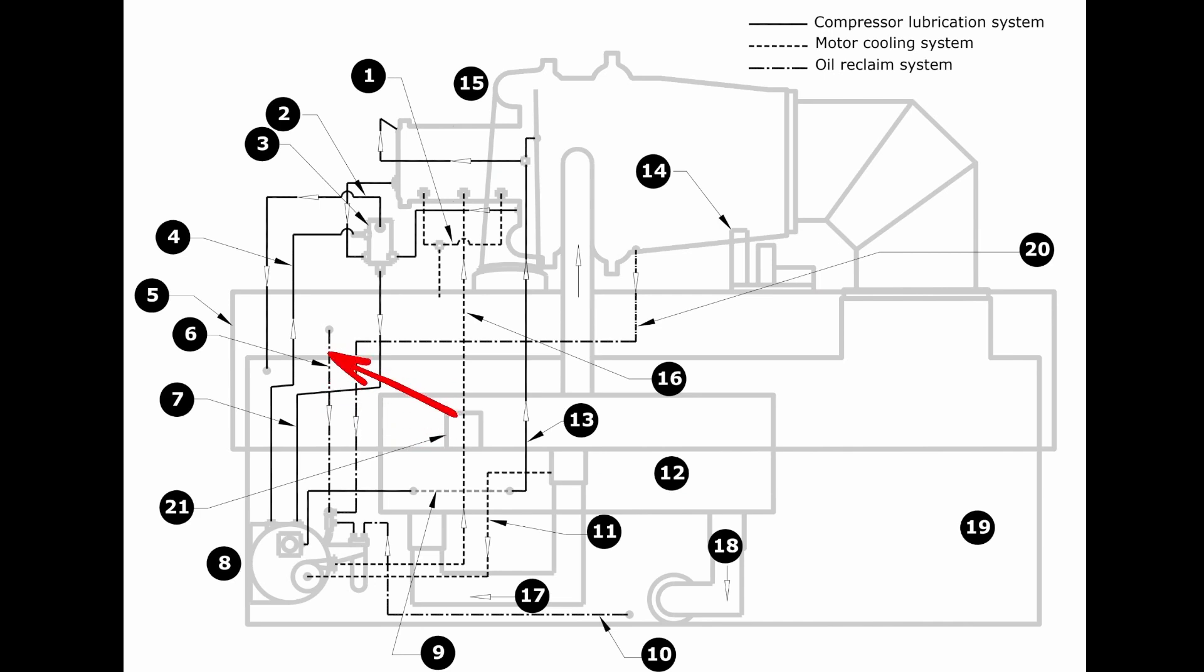I'll cover the eductor quickly here as well. The eductor system, another term for this that's also commonly known, is a jet pump. Essentially, we need to make sure that we're getting our oil back that gets trapped into the system. Oil that gets trapped in our evaporator and oil that gets caught in our suction nose cone need to be able to return back to our oil sump, otherwise it will create other heat exchange issues.